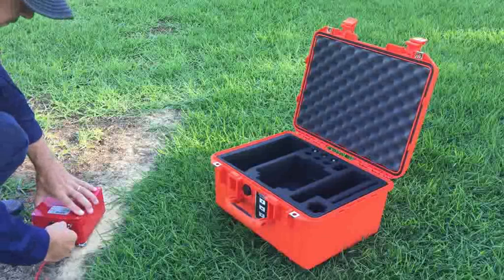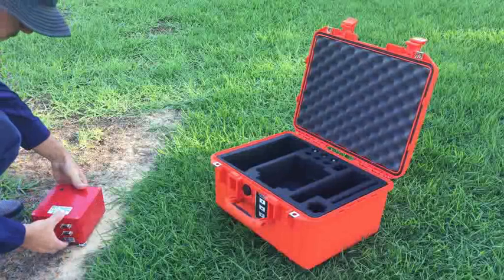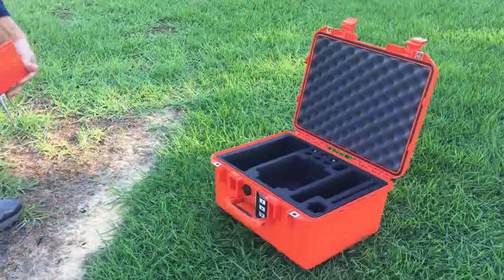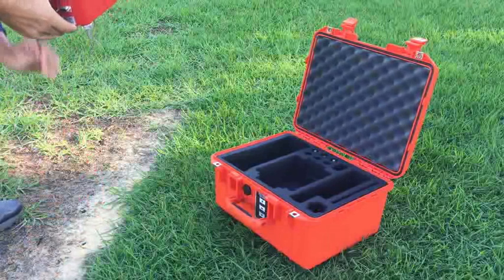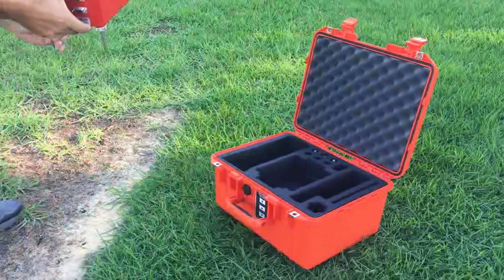After you are done with data acquisition, you unplug the cables and take the instrument out of the ground. The pins don't need to come off — there is enough vertical space in the Pelican case for the instrument with pins attached to be inserted back in.